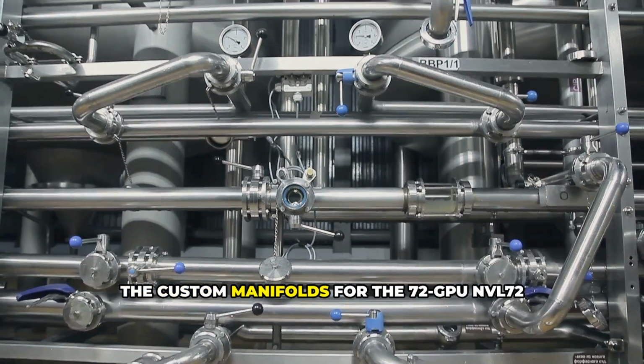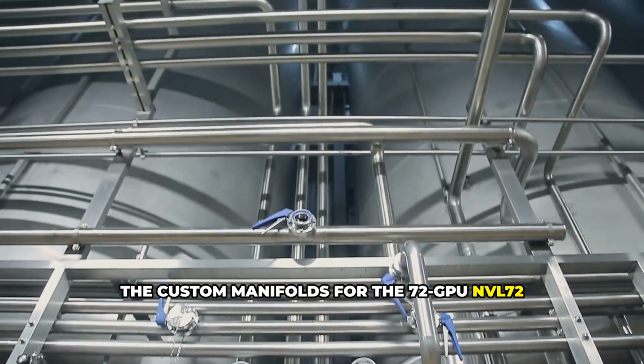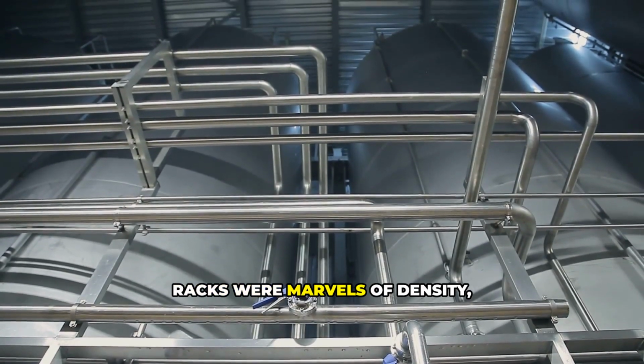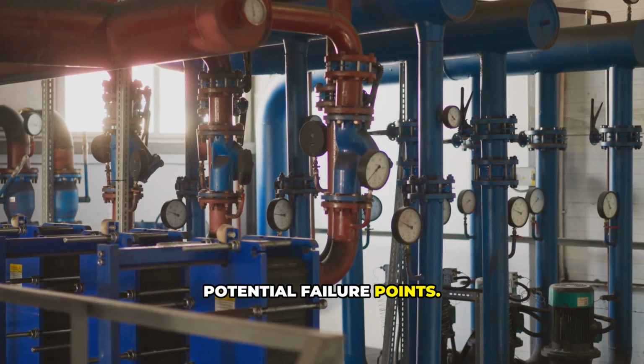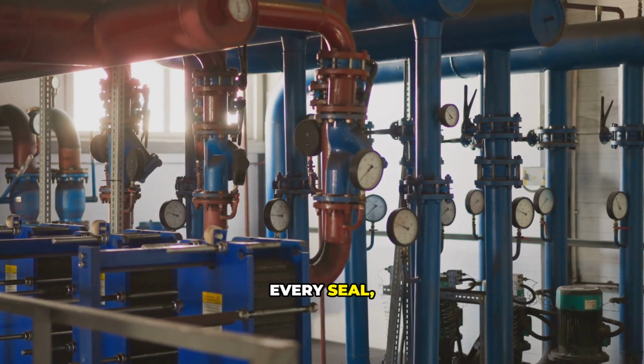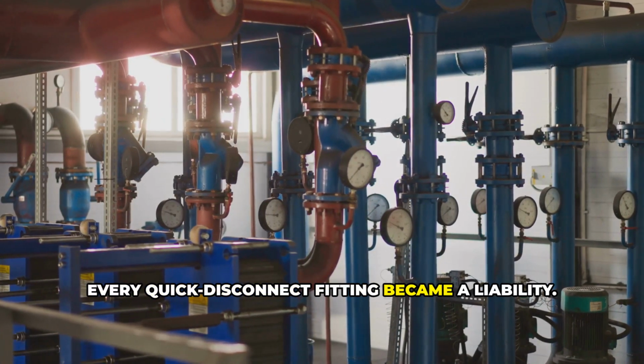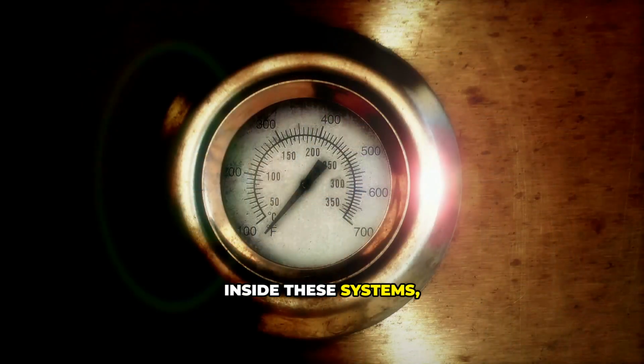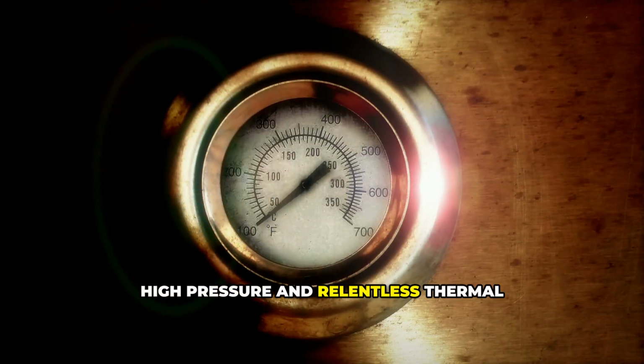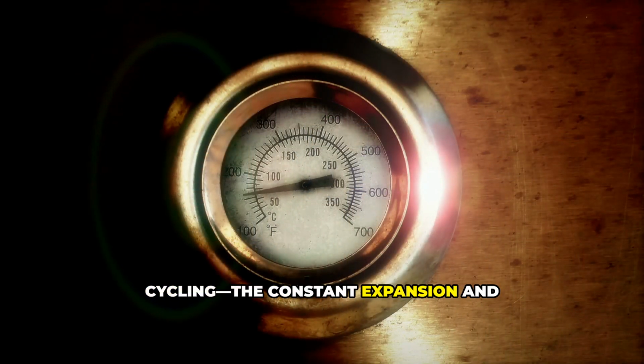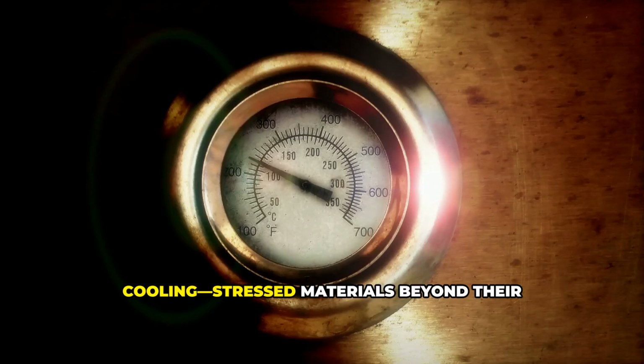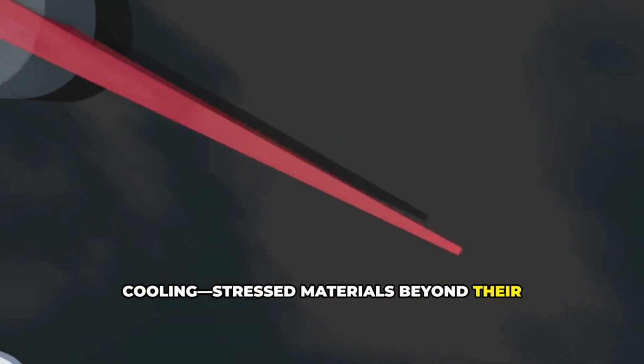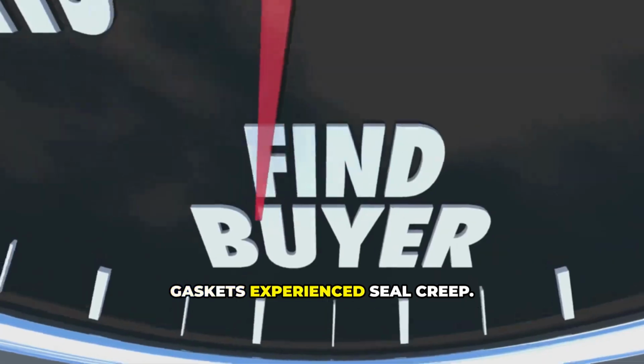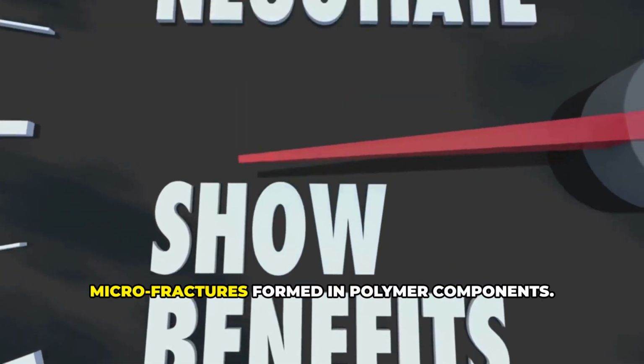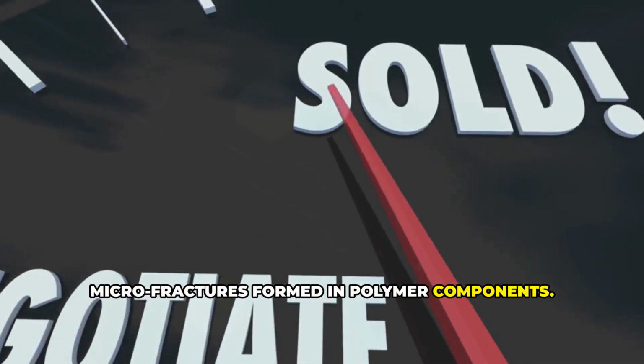The custom manifolds for the 72 GPU NVL72 racks were marvels of density, but they also concentrated hundreds of potential failure points. Every joint, every seal, every quick disconnect fitting became a liability. Inside these systems, high pressure and relentless thermal cycling, the constant expansion and contraction from heating and cooling, stressed materials beyond their designed limits. Gaskets experienced seal creep. Microfractures formed in polymer components.